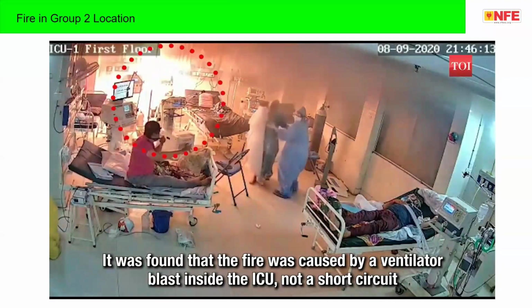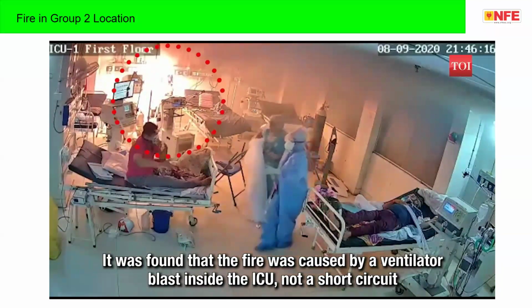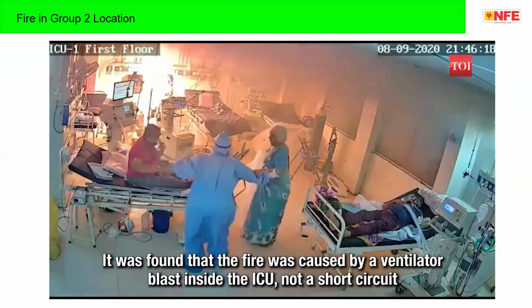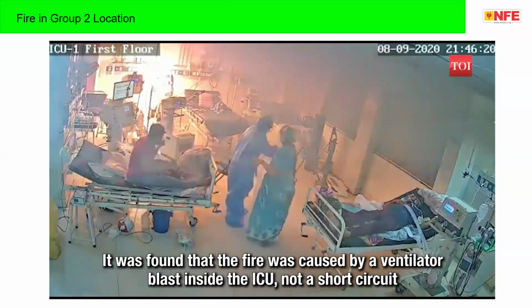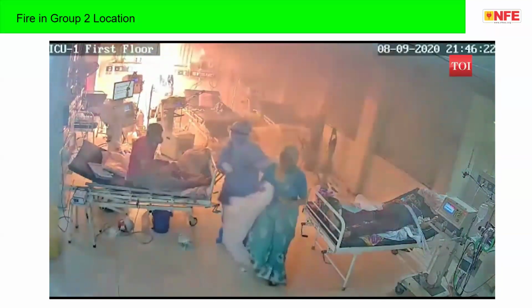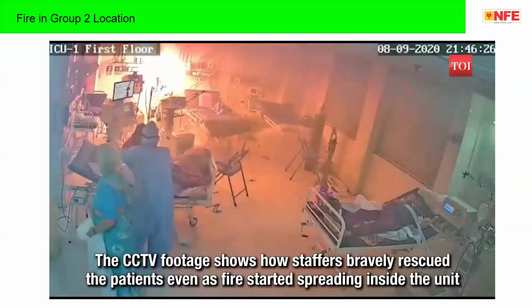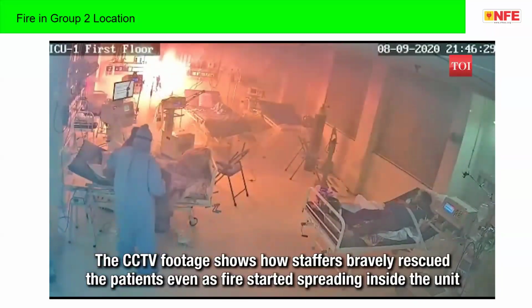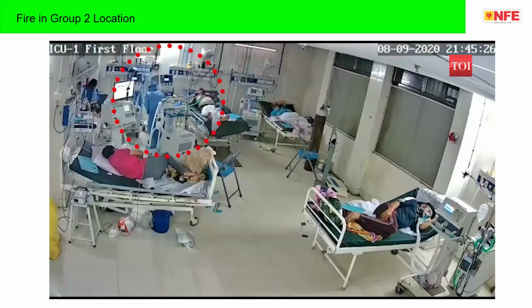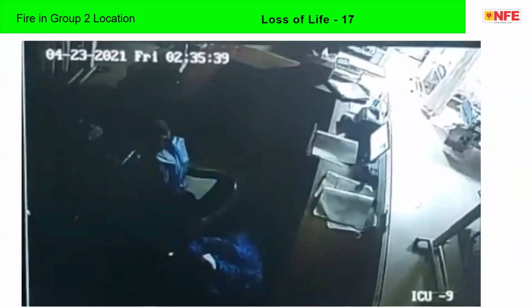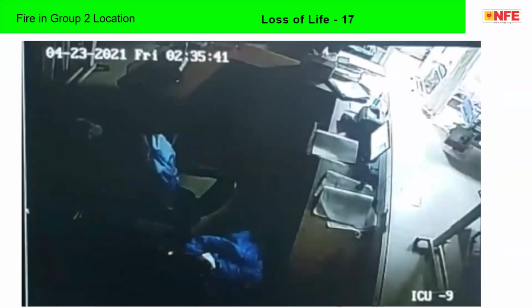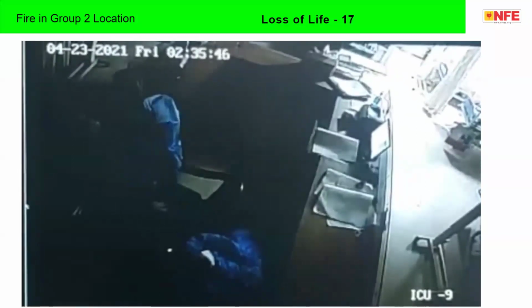Most often, if you look at the reports of such incidents, it always says the fire is due to overload. As electrical engineers, please note that overload cannot ignite fire. During overload or short circuit, the device should trip. Protective devices are installed in the electrical circuit to trip. So electricity is not supposed to create fire.